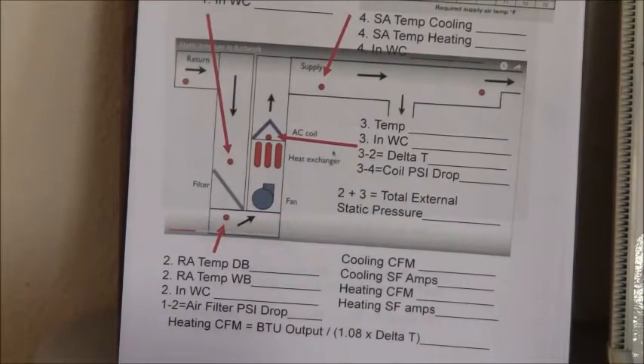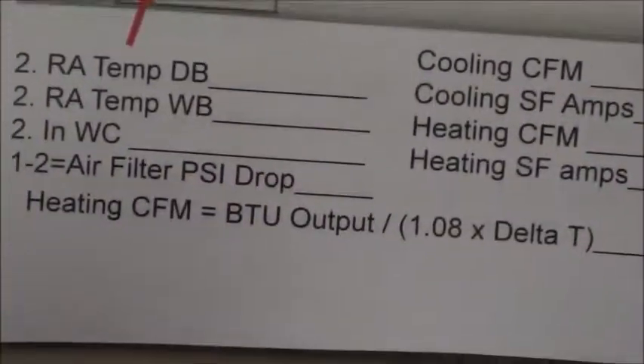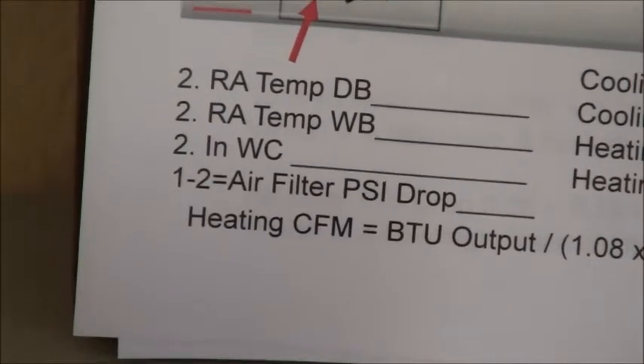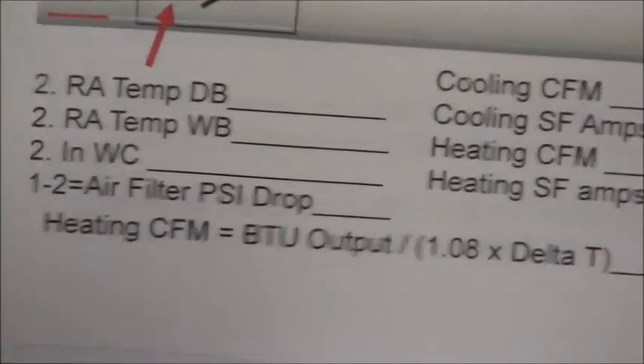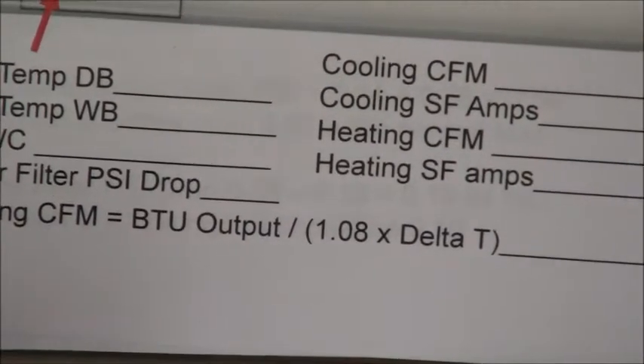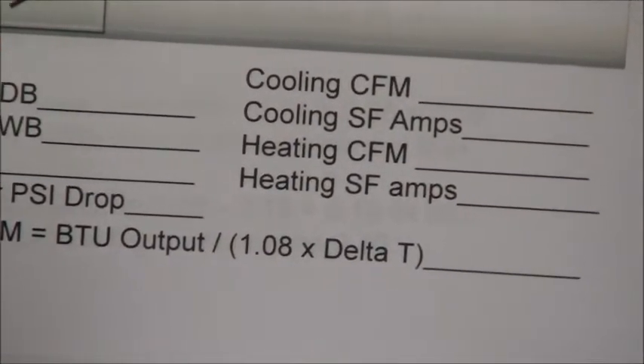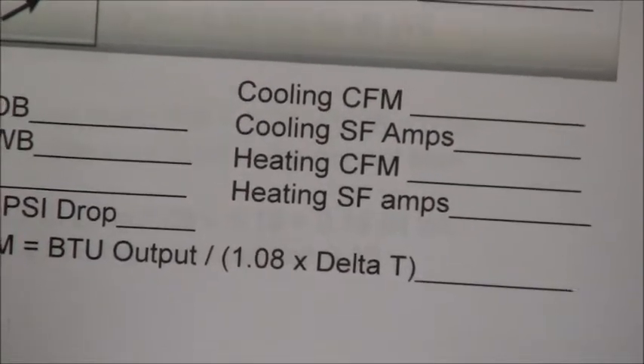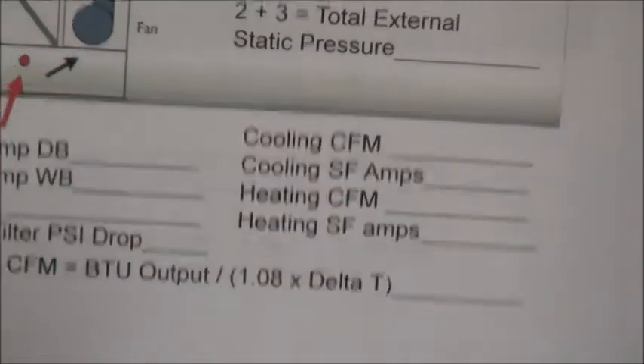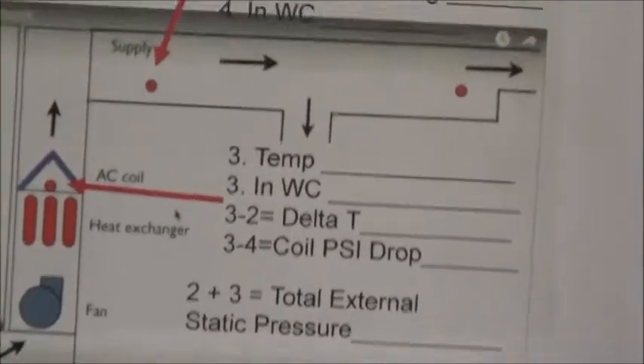To get the heating CFM, you can see here I can figure out the heating CFM equals the BTU output divided by parentheses 1.08 times the delta T. And we'll go through all that so that you get exactly what it is. Your delta T is right there once we fill that out. So we'll go through this entire checklist.